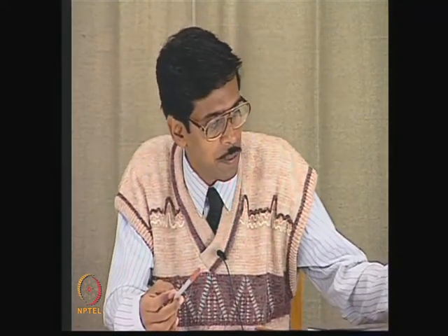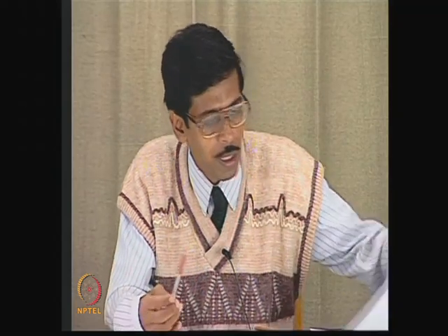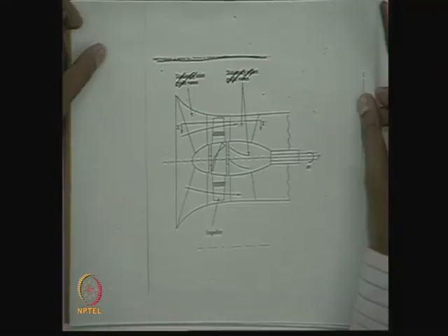So, an axial flow pump is a pump where the flow is almost in the axial direction. That means the inlet and outlet of the fluid do not vary in their radial location from the axis of rotation. We have discussed this in the axial flow turbine also. This definition holds good as well for any axial flow machine. So, therefore, an axial flow pump can be thought of as a converse to an axial flow turbine or a propeller turbine. And we can just have a look at how an axial flow pump looks.